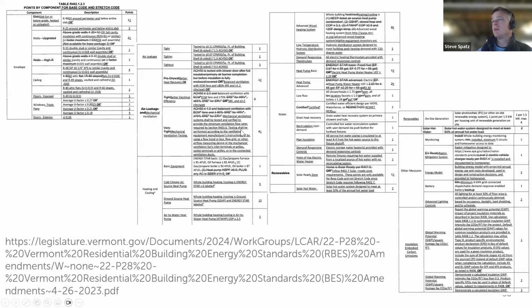Mechanical ventilation, improving upon the sensible recovery efficiency of the minimum performance requirements, earns points, as well as doing commissioning of ventilation systems once they're installed. So you're basically verifying flows, that you're getting the appropriate flows for supply and exhaust throughout the house.